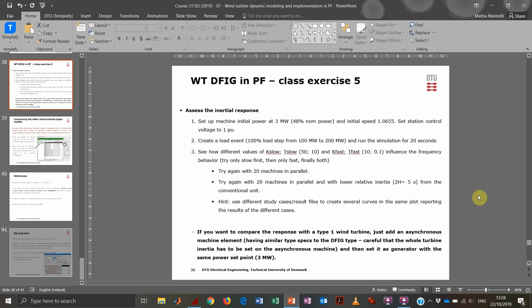Let's focus on the last exercise for the wind turbine class. In this exercise we want to assess the inertial response of the wind turbine and see how much we can affect the frequency in the system during a load or generation event. We will set the machine at 3 megawatts, initiate the dynamic with a 100% load increase from 100 to 200 megawatts, run the simulation for 20 seconds, and observe how different controller gains affect how much kinetic energy we can pull from the rotor to support the frequency dynamic.